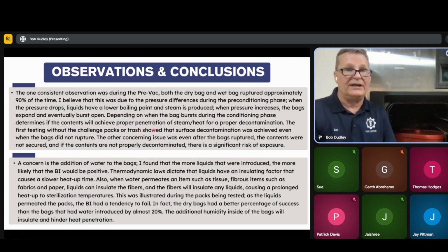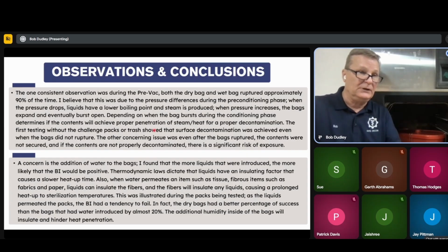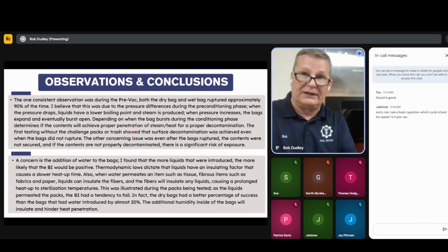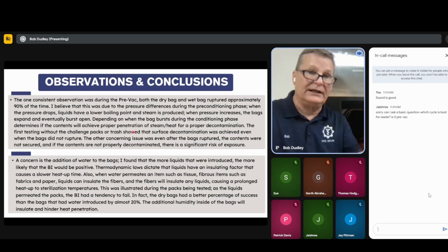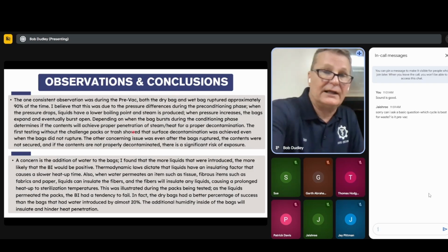One consistent observation is during the pre-vac cycle, both the wet and the dry bag, they did rupture about 90% of the time. We just don't know when they burst and at what point. I think when they fail, it was later in the preconditioning that you did it. And if you don't get that preconditioning, you're not going to get the penetration of the heat, which is critical. And if you get that liquid block of the heat, it's going to insulate the interior of it, and then you're going to have the problems.